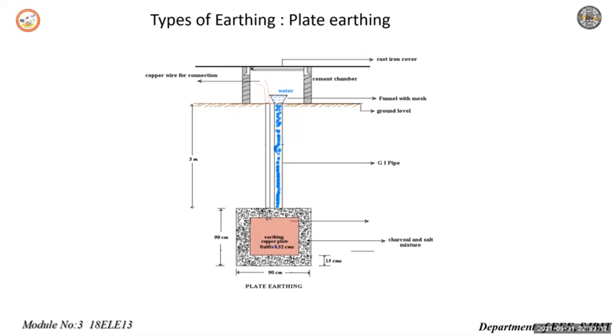Earthing is achieved by connecting the electrical appliances or components to earth by employing a good conductor called an earth electrode. This ensures a very low resistance path from the appliance to the earth. The various methods of earthing are plate earthing and pipe earthing. Let us discuss the two methods of earthing which are very commonly used in practice. The first one is plate earthing. You can look at the diagram.